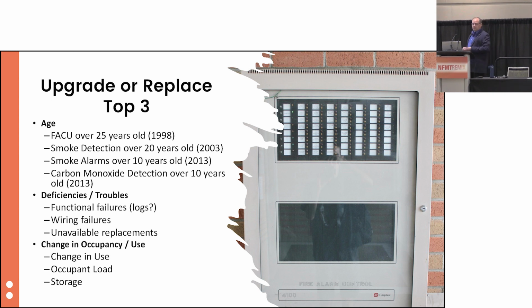And unavailable replacements. The picture you see here, you may or may not be familiar with. That's a Simplex 4100 annunciator, released in 1988. The technology behind that is very solid, it's a very good panel, and it will still work today. But if that switch, that light, or that control board behind it fails, none of those parts are available today for replacement. You'd have to replace that entire panel to get it back up to speed.